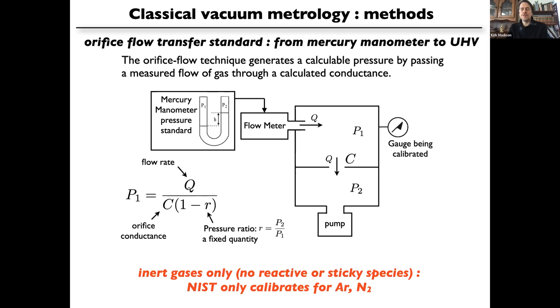So clearly, if this mass flow which is coming in is a sticky gas, the flow rate out of the flow meter will not necessarily be the flow rate through the conductance hole to the orifice. In particular, if the gas is sticking to the walls, all bets are off. The pressure P1 is related to, but not uniquely determined by the flow rate Q in, because you can't relate it with respect to the conductance. If all the gas sticks to the walls, you have no idea what P1 is. So this means that you can only calibrate gases which are basically non-reactive, non-sticky, and only inert gases. NIST only calibrates for argon and nitrogen at this point.